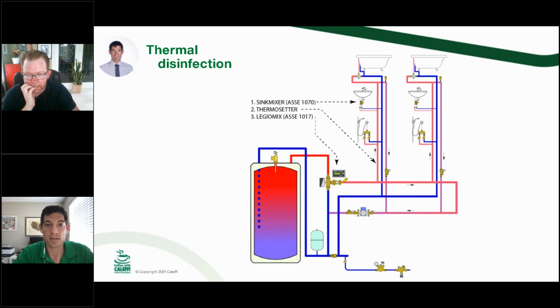But instead, you could try thermal disinfection with the thermostatic mixing valve, and what you would do is go down to the mechanical room, turn it up to 180 degrees. You've got the point of use protection all the way around the building, and then put your hand on the return and wait until it comes back hot enough that you can't grab it. That's not scientific enough that we would trust that, or trust somebody to do that in order to disinfect the line. So we program that into the control and let it automate that at 3 in the morning on a Saturday.